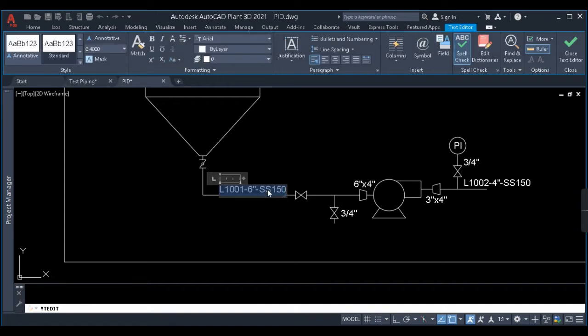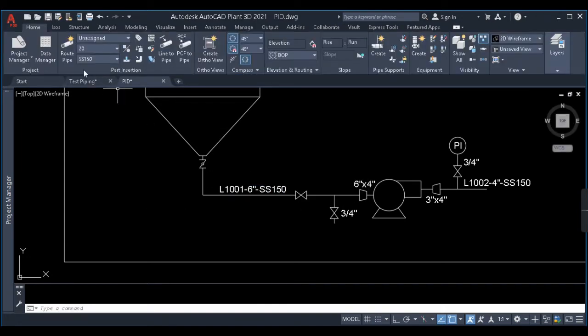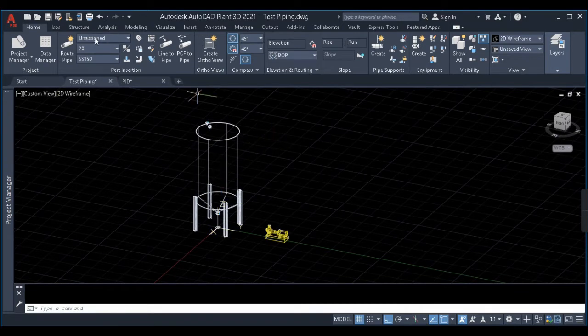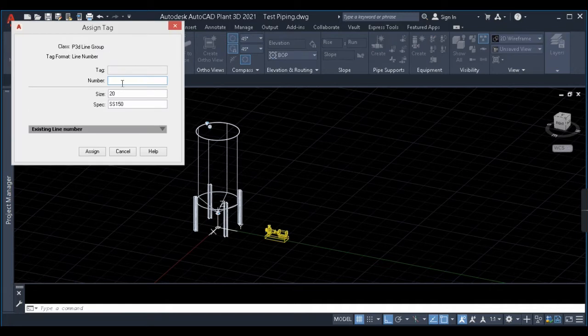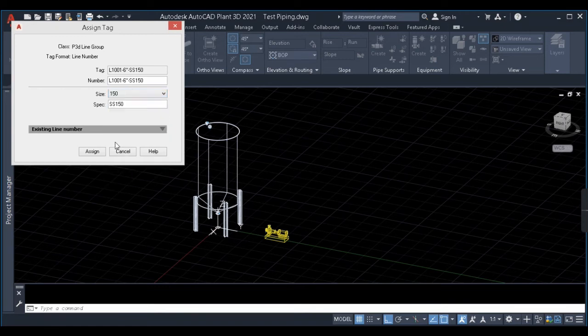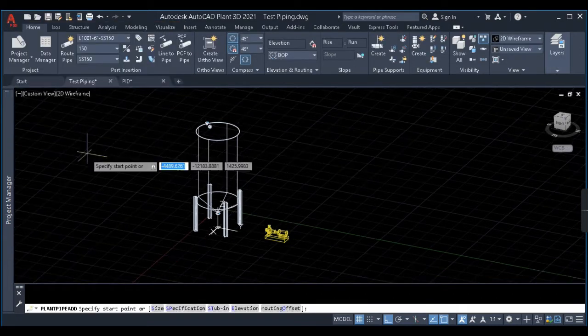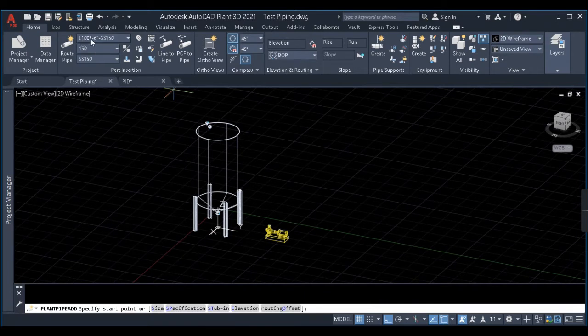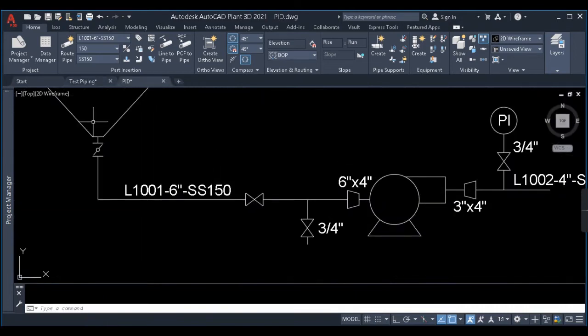I'll copy this line number — it's just a random line number, you can refer to any plant P&ID. On the top, click 'Route New Line Number.' It asks for the number, so I enter the line number. Next it asks for the size — the line is 6 inch, that is 150 — and I'll leave the spec as SS 150 and click Assign. Now my line number is showing.